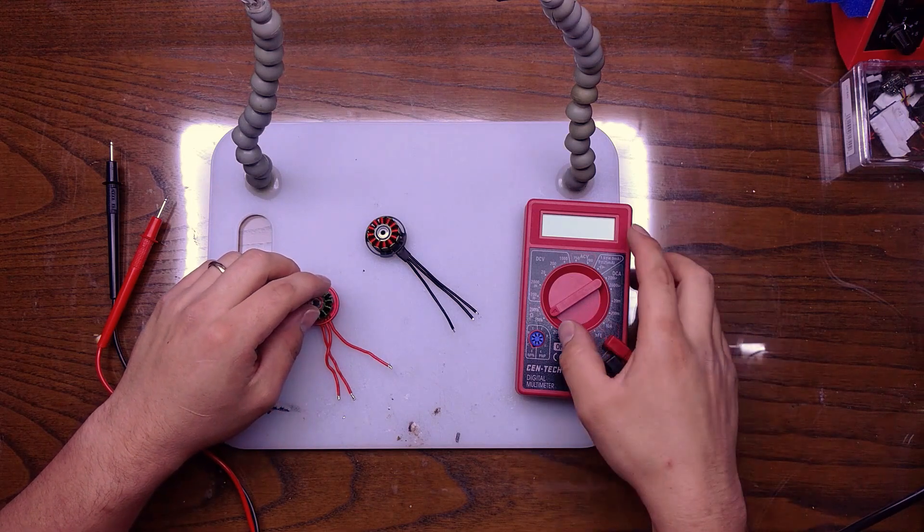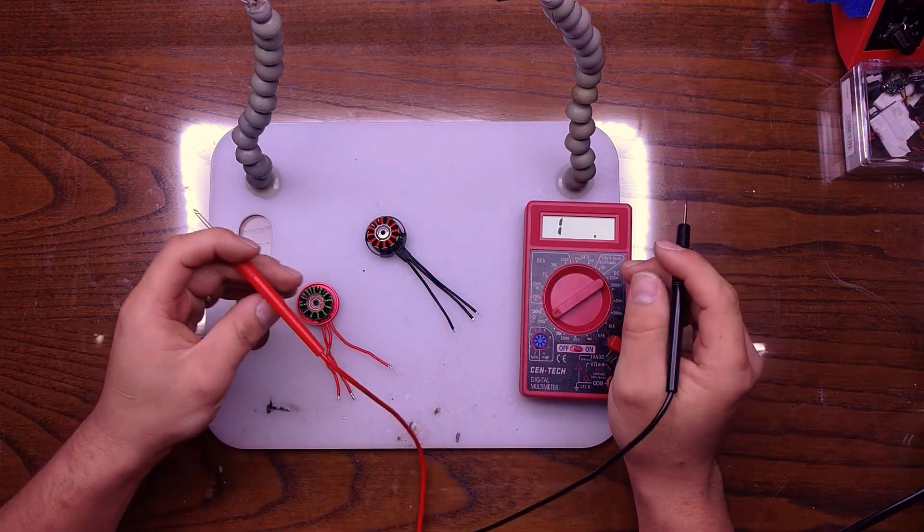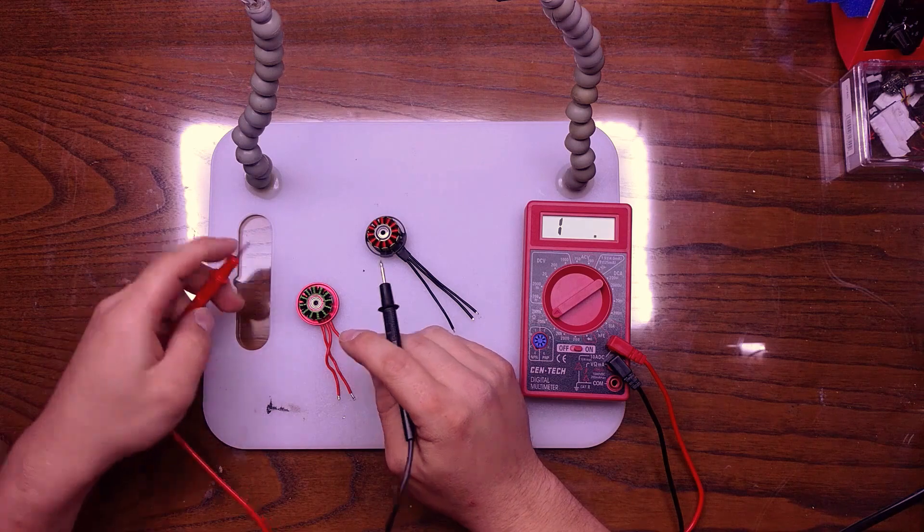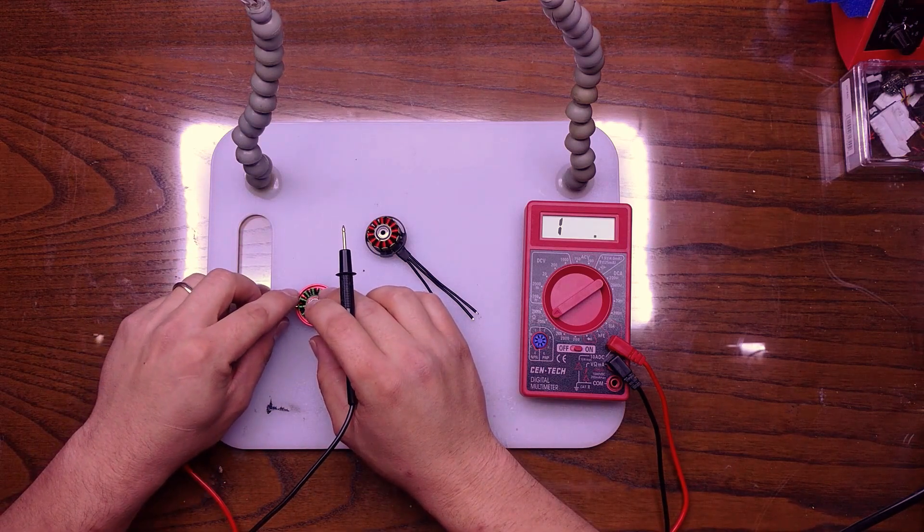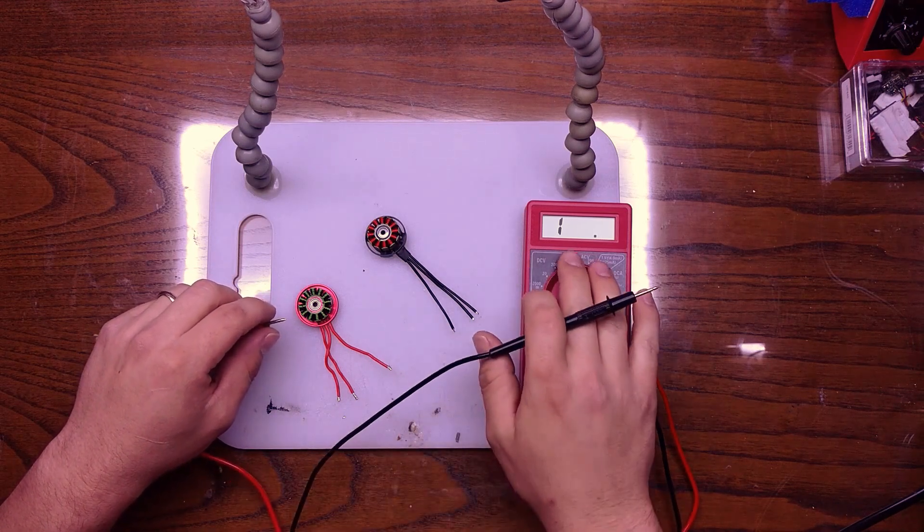So simply, all you have to do is check for continuity. I have a $5 multimeter here. You can pick one up at Harbor Freight, Walmart, anything like that. And all you're going to do is make sure that you have a connection to your stator and then touch one of these leads and see if you have continuity.